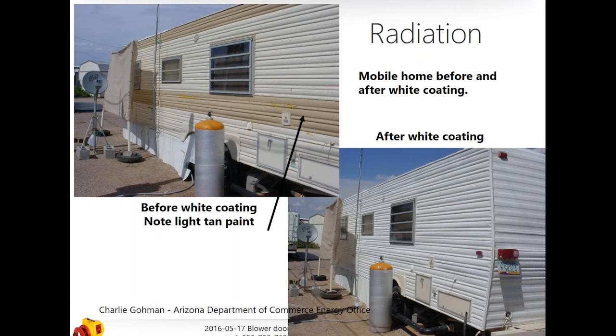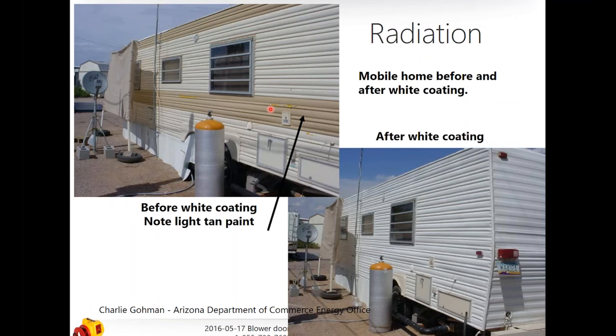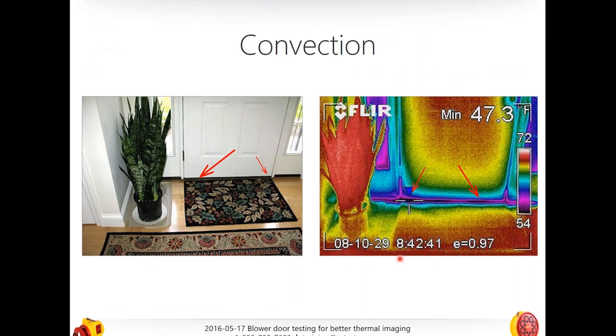Emission, absorption, reflection, and transmission are very important terminologies if you want to be a savvy thermographer. When we're talking about thermography and infrared, we're always talking about radiation — what we're actually seeing is heat being radiated off an object. Even if we're finding problems with conductive or convective heat loss, what that IR camera is seeing is heat being radiated or emitted from a solid object. That's really important to understand if you're going to do this well.